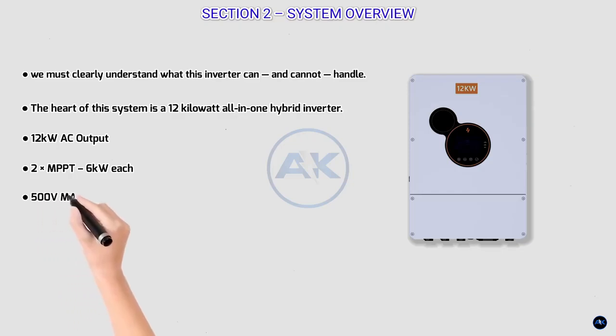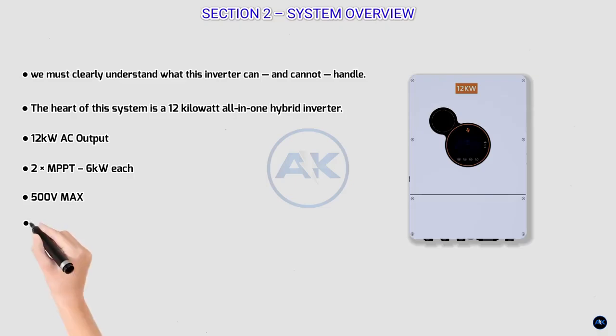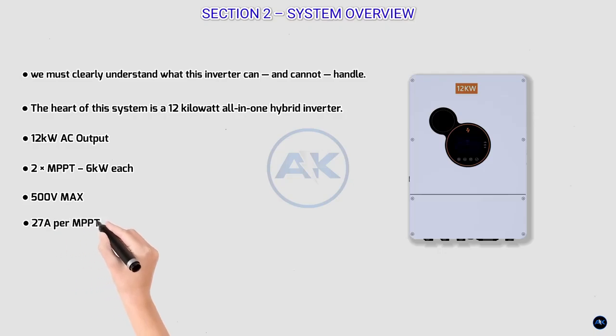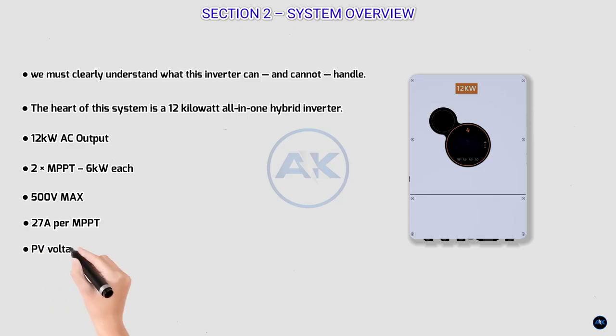The maximum PV voltage allowed on this inverter is 500 volts. Go above this, even for a moment on a cold winter morning, and you risk permanent inverter damage. The maximum PV current per MPPT is 27 amps. Exceeding this won't usually destroy the inverter instantly, but it forces the MPPT to clamp or shut down, wasting power and stressing internal components. The inverter's PV operating voltage window is 120 to 500 volts. Your solar strings must stay inside this range during all seasons, from summer heat to winter frost.